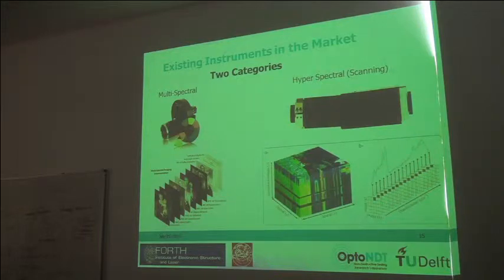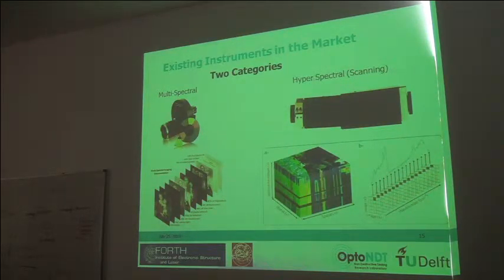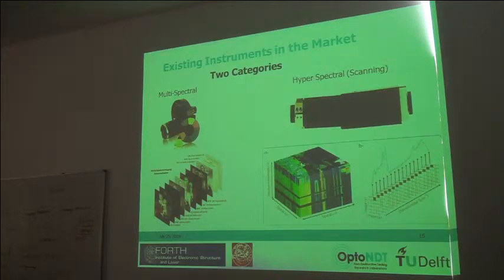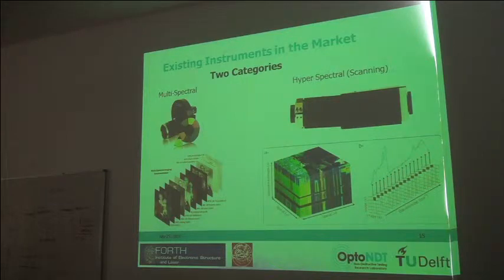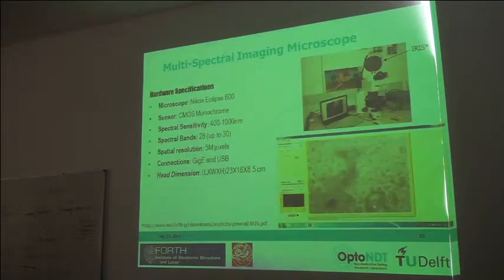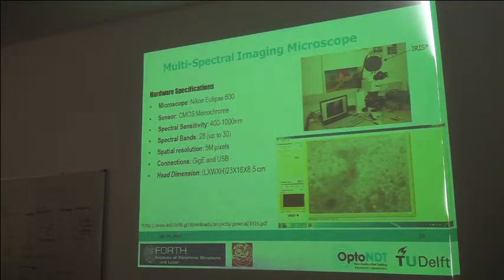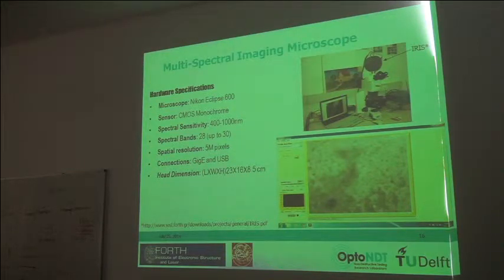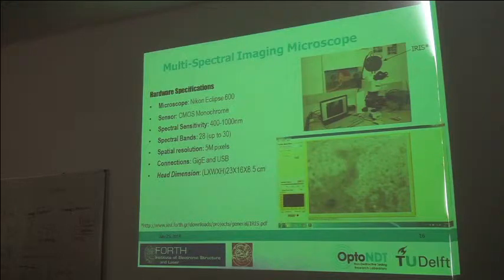The instruments available for spectral imaging are divided into two categories: multispectral and hyperspectral. Multispectral refers to a number of filters — a few tens of spectral bands, approximately up to 20 or 30. Hyperspectral allows you to tune to any wavelength with steps of every one or two nanometers. At our lab, we developed a system called IRIS: a simple multispectral imaging sensor incorporating approximately 30 filters covering 400nm up to 1 micron, with 5-megapixel resolution, and coupled with a microscope it can provide information about biological samples.